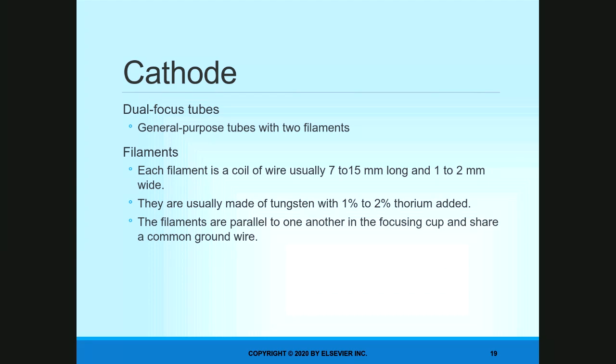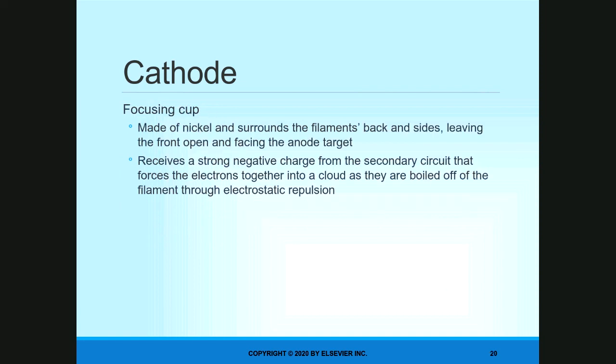And when you put these two metals together, because it's an alloy, it increases the strength of the filament, so you're actually helping to extend the life of those filaments. Notice it says that the filaments are situated parallel to each other in the focusing cup, and they share a common ground wire, meaning they're next to each other in the focusing cup, but you can only choose either the large or small filament. You can't choose both at the same time.